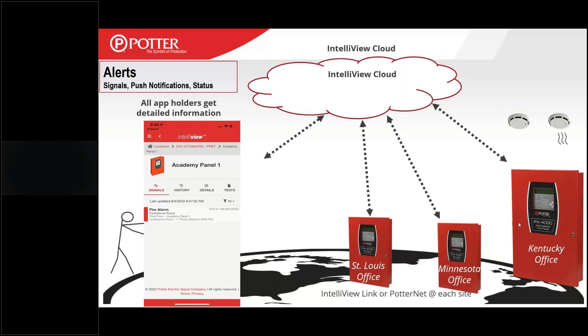There is really no control in IntelliView. The only time you can control a panel in IntelliView is if you put the panel into a walk test mode. You don't have to put a panel in walk test mode to use our test feature, but you do need to if you want any control of the panel. All of these things are based on our UL restrictions — if you put the panel in walk test mode, you're more in a commissioning or maintenance mode and not a monitoring mode.